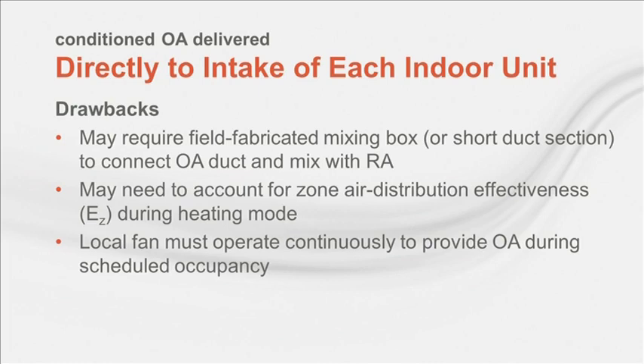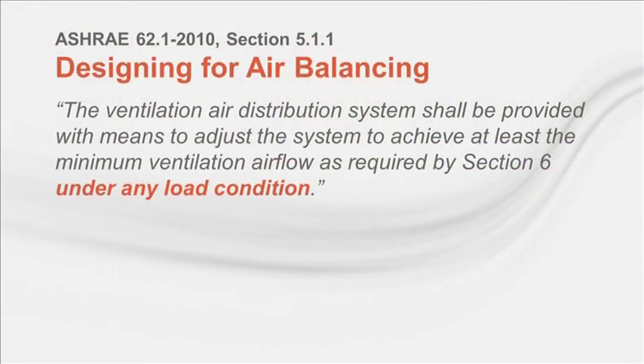If you cycle the indoor fan on and off, or if you vary its speed, less outdoor air will be delivered to the zone. So to ensure that you get the required outdoor airflow, you either need to run the indoor unit fan at a constant speed, or you could add a pressure-independent damper like a VAV box to the outdoor air duct. Then as the indoor fan speed changes, this damper opens or closes to maintain the same outdoor airflow regardless of fan speed. Now, Standard 62.1 speaks to this concern by emphasizing that the ventilation air distribution system needs to provide each space with its minimum ventilation airflow under any load condition.